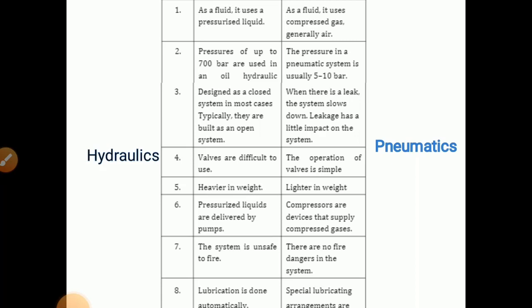Hydraulic systems are heavier in weight, pneumatic systems are lighter in weight. In hydraulic system pressurized liquids are delivered by pumps. But in pneumatic system we require compressors to supply compressed gases. In hydraulic system the system is unsafe to fire, but in pneumatic system there is no fire dangers in the system. In hydraulic system lubrication is done automatically because oil is used everywhere, but in pneumatic system we require special lubricating arrangements.